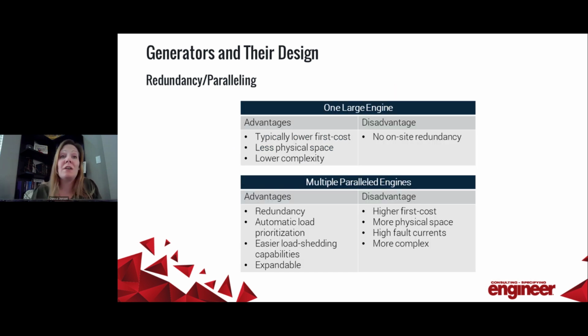Of course, there's pros and cons to everything, and there are certainly some great advantages to having a system with just one large engine and the temporary tap can, as I mentioned earlier, but this is a code minimum design. So first off, this type of system topology typically is a lower first cost. It also takes up less space, and overall, it's just a very simplistic design. But the biggest disadvantage with this arrangement is that you have no on-site redundancy. So even in the event of a failure, you're basically going to have to wait to get a portable system so that you can get your critical loads back online.